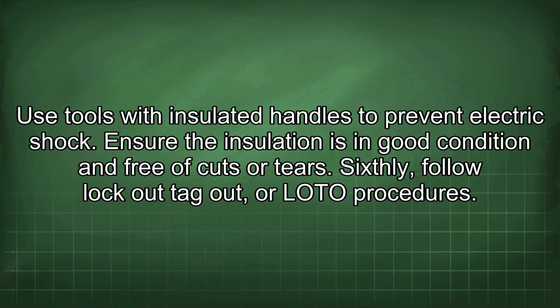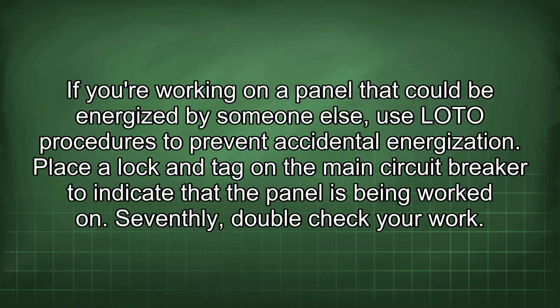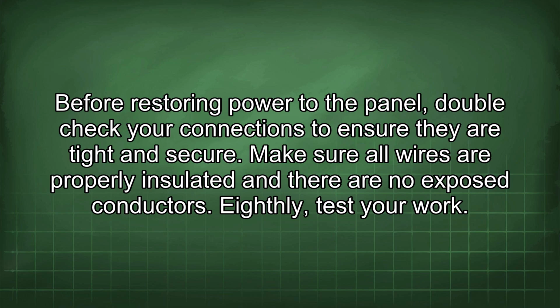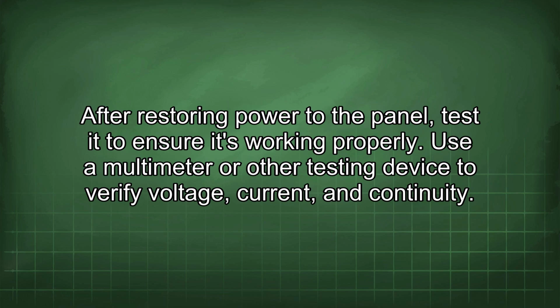Sixthly, follow lockout, tagout, or LOTO procedures. If you are working on a panel that could be energized by someone else, use LOTO procedures to prevent accidental energization. Place a lock and tag on the main circuit breaker to indicate that the panel is being worked on. Seventhly, double-check your work. Before restoring power to the panel, double-check your connections to ensure they're tight and secure. Make sure all wires are properly insulated and there are no exposed conductors. Eighthly, test your work. After restoring power to the panel, test it to ensure it's working properly. Use a multimeter or other testing device to verify voltage, current, and continuity.